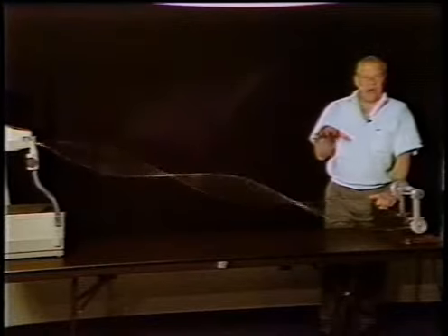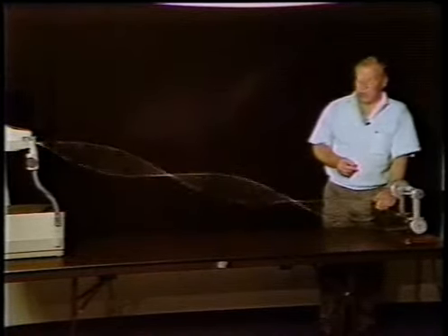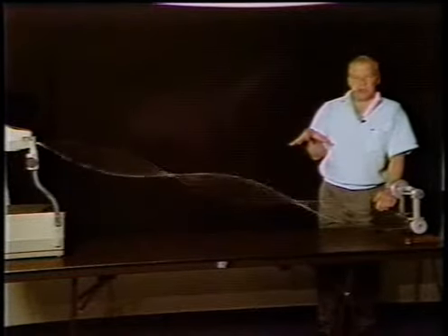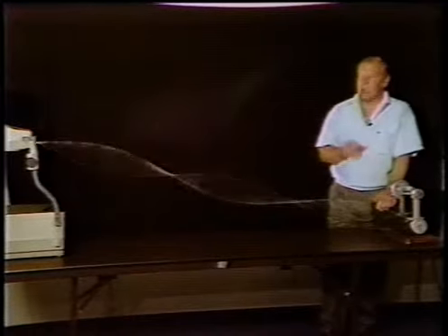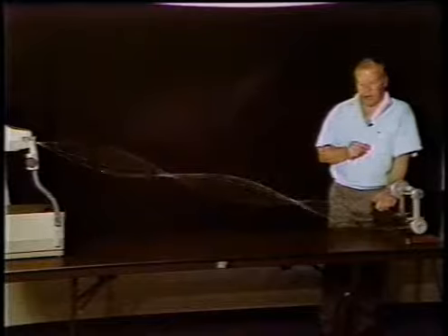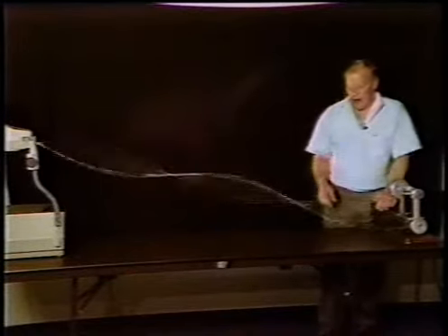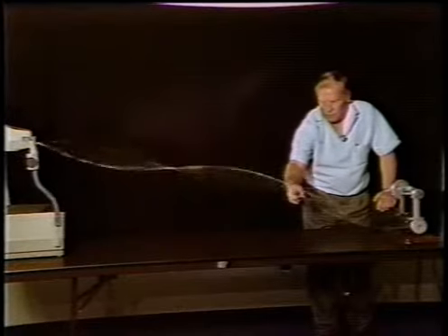If you identify a problem as resonance, obviously the question is, well, how am I going to solve that problem? The natural frequency of any system can be easily changed by either changing the mass or the stiffness of the system. Generally, a change in stiffness is the easiest correction to make. However, let's see what happens if I happen to make a stiffness change right here at the nodal point.